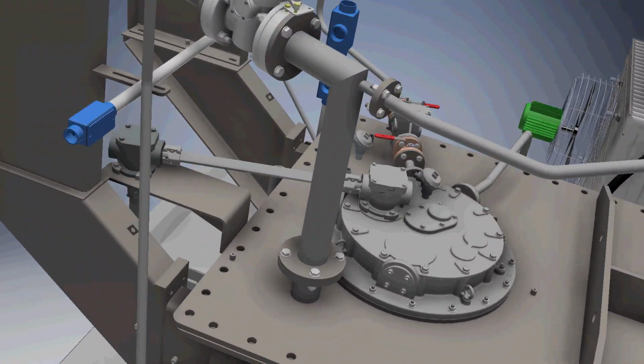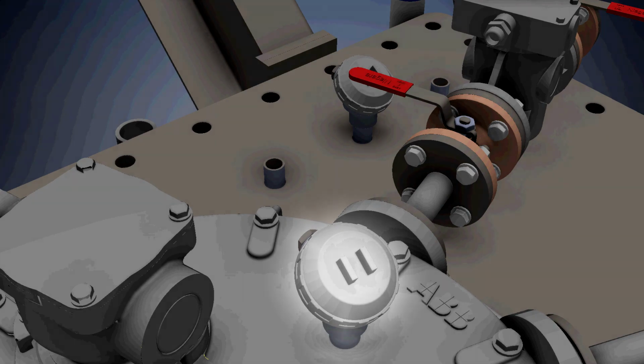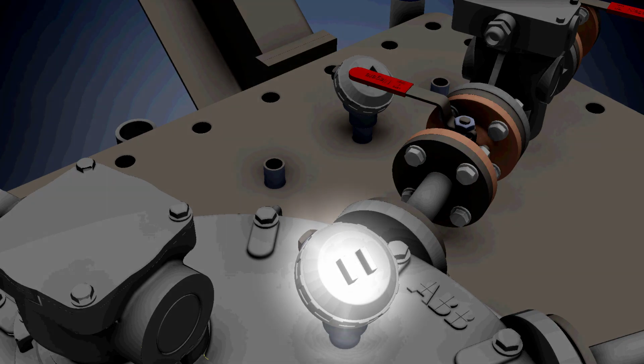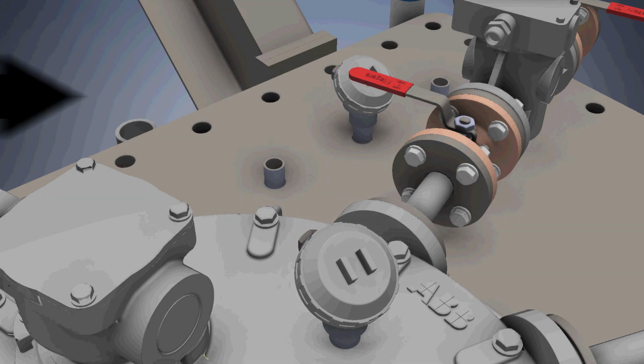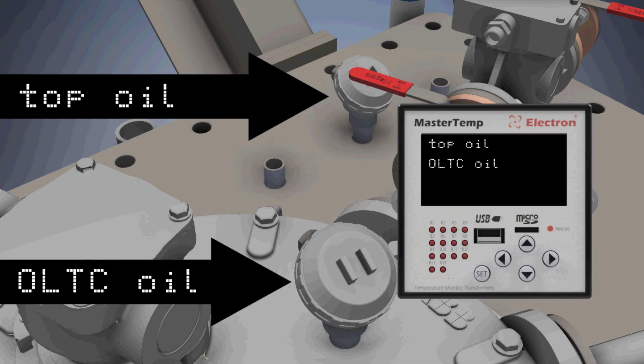We can also use one of the sensors to monitor tap changer oil. In this configuration it is possible to monitor the differential temperature between transformer oil and tap changer oil, and to set off an alarm if any malfunction occurs during the tap changer operation that causes such differential.